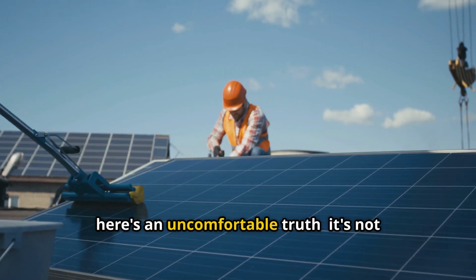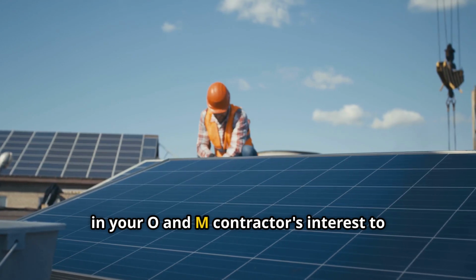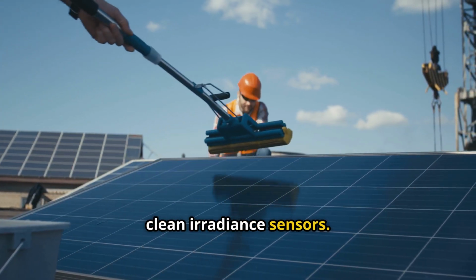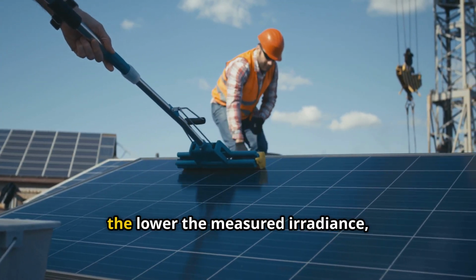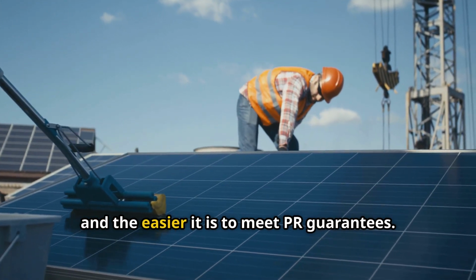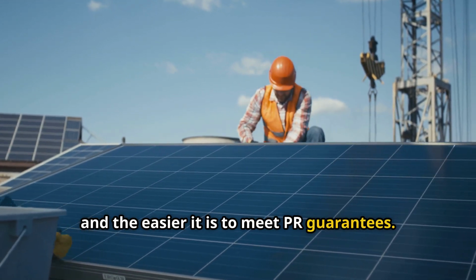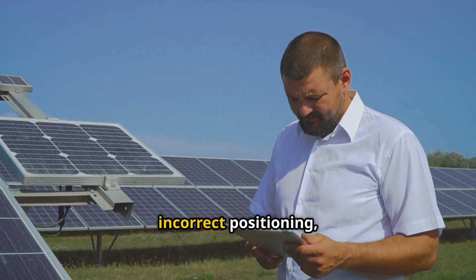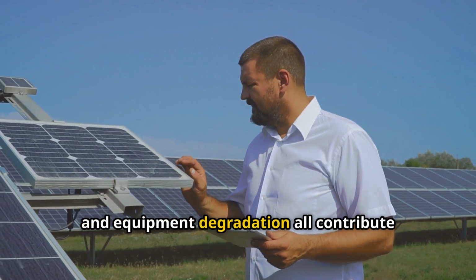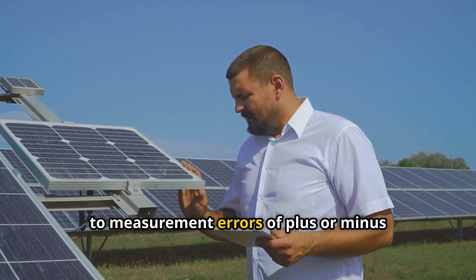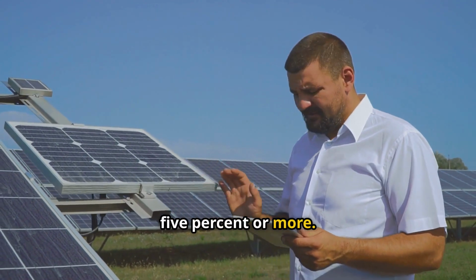Now here's an uncomfortable truth. It's not in your O&M contractor's interest to clean irradiance sensors. The dirtier the sensor, the lower the measured irradiance, and the easier it is to meet PR guarantees. Sensor calibration drift, incorrect positioning, and equipment degradation all contribute to measurement errors of plus or minus 5% or more.